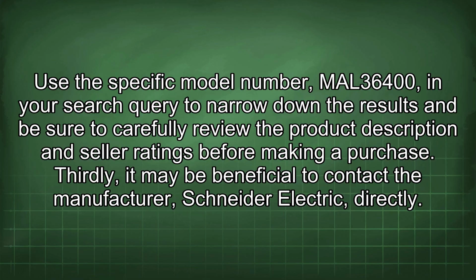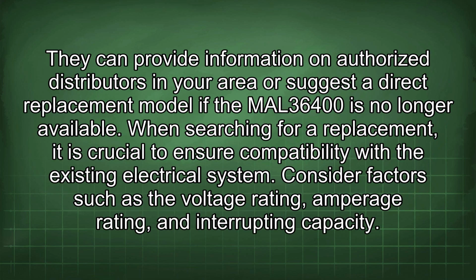Thirdly, it may be beneficial to contact the manufacturer Schneider Electric directly. They can provide information on authorized distributors in your area or suggest a direct replacement model if the MAL36400 is no longer available. When searching for a replacement, it is crucial to ensure compatibility with the existing electrical system. Consider factors such as the voltage rating, amperage rating, and interrupting capacity.